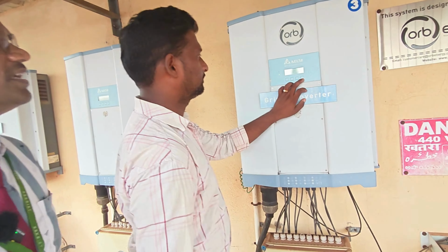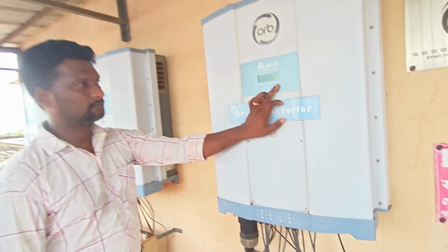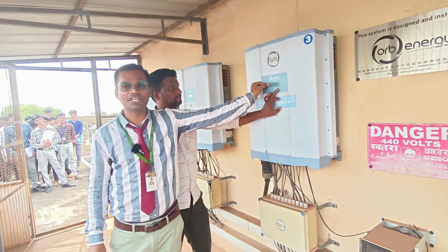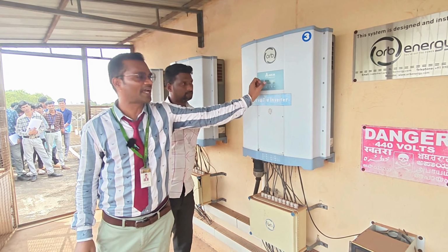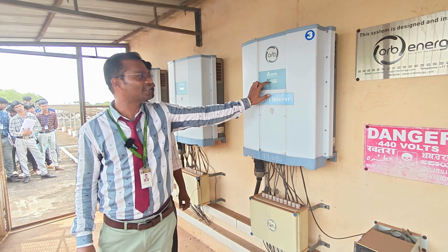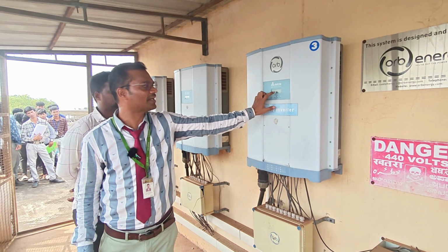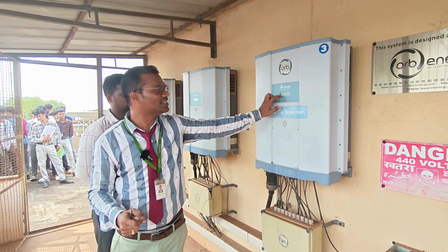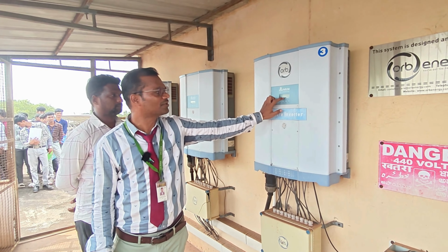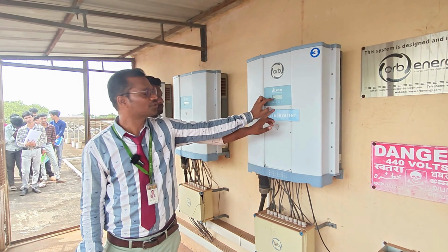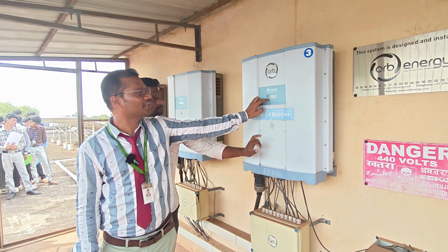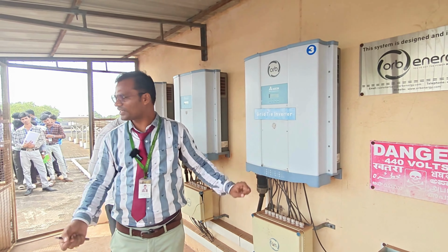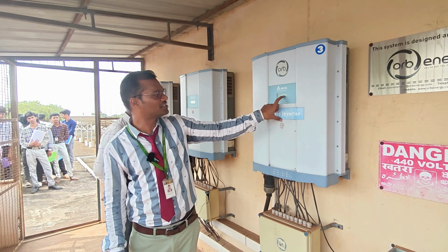When you go into the log info, the meter will display. I think it is visible to you. This is AC input, line 1, line 2, line 3. The line to line voltages are 409, 407 and 408 volts. The corresponding currents are 21 ampere, 21 ampere and 20 ampere, so each phase is getting loaded. The overall power factor of the system, we have done the experiment, is 0.9.